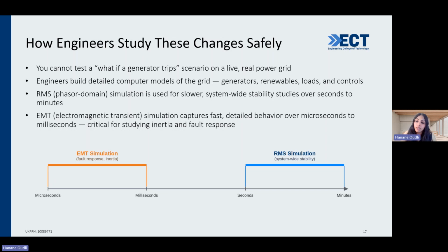However, EMT, which stands for electromagnetic transient, goes deeper, modeling instantaneous waveforms rather than phasors. It's valuable for inverter controls, switching behavior, fault response, and weak grid behavior over very short time scales. So I wouldn't say either is better.